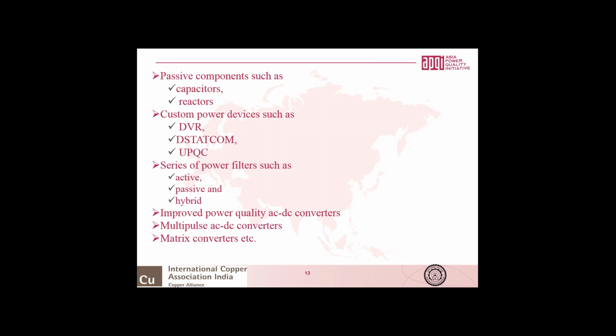But we have a solution for the forthcoming generation of equipment, that in many of the equipment we can modify the input stage itself by using improved power quality AC-DC converters. It means these improved power quality converters at the input stage are supposed to eliminate harmonics as well as the reactive power burden provided, of course, by those equipment in which we are using them. There are plenty of examples, maybe a computer power supply, adjustable speed drives. Starting from a fraction of a watt to 700 megawatt are the examples where we can use or we are using these improved power quality AC-DC converters.